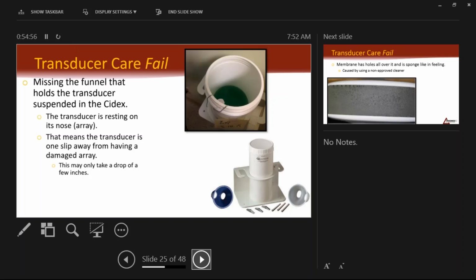If sites aren't using Trophons yet, and they're still using Cidex, one thing we never want to happen is for those probes to rest on the nose. This is a picture of a place that didn't have a funnel to hold the probe in place. So we always want that. Two bad things about that. A, you put it in there, you drop it the last inch, you keep doing that over and over and over, eventually you're going to damage the array. B, when it's resting on its nose, that part that's resting isn't really getting Cidex on it. So there's a potential that the very tip isn't getting cleaned. Probably is, but you never know. So if you see this, they should have a funnel. In some way, that probe should be suspended in the Cidex or whatever disinfectant they're using.